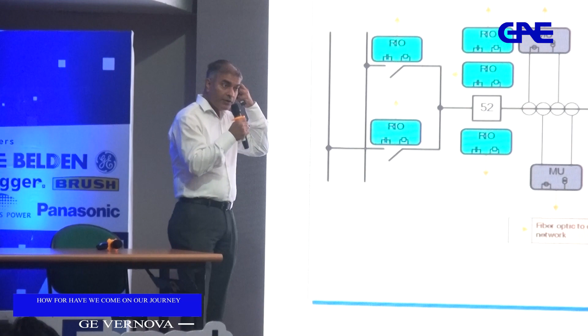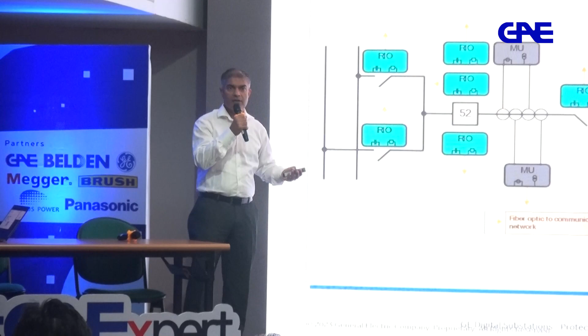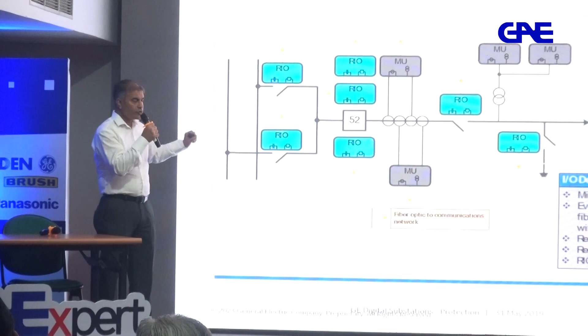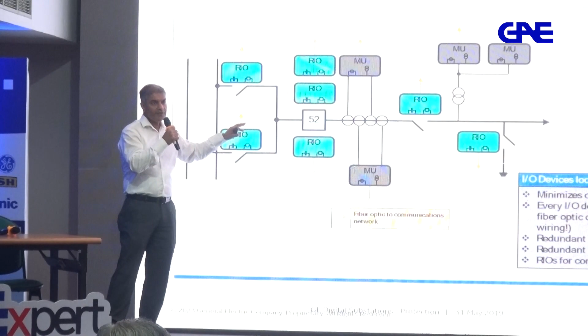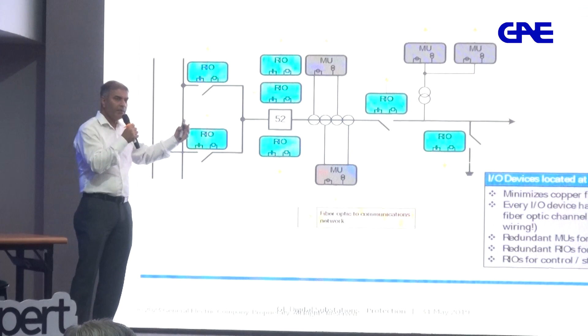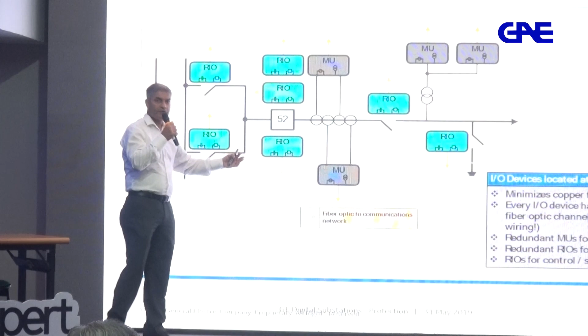So basically how you execute, right? So basically pick a typical wiring architecture, and there are a number of options, right? If you think about outdoor wiring, the wiring in the outdoor cubicle, one option is that you have a remote interface unit, remote IO unit for each device. So for each disconnector, for each circuit breaker, you have a separate remote IO unit. For analog interface, for CT, PT, you have a merging unit. So this is one approach. So that minimizes the copper cabling. Every IO device has dedicated fiber optic. So this is one such example.